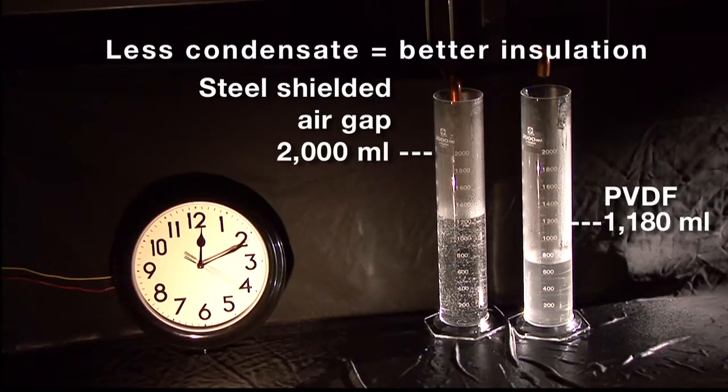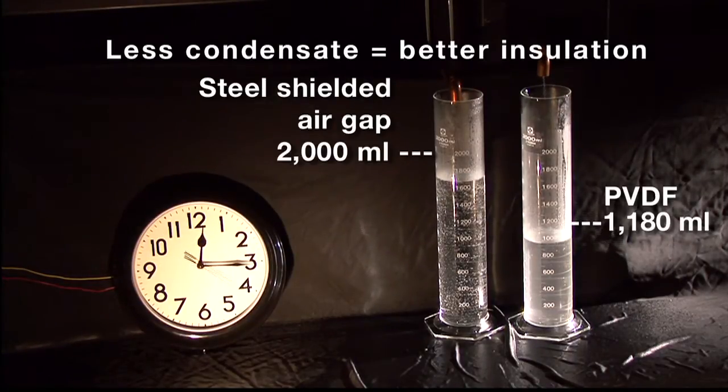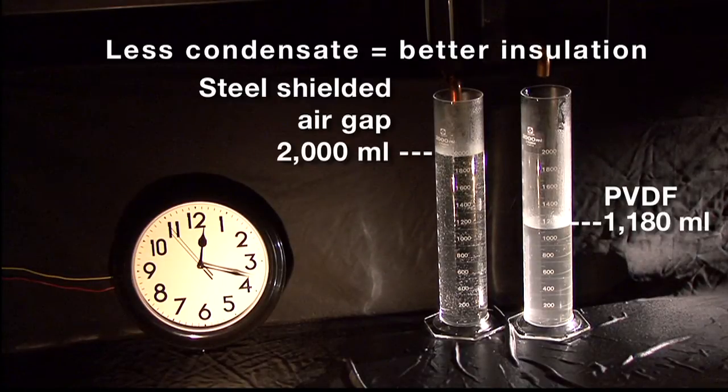In fact, tests performed when we were establishing PVDF's insulating performance guarantee showed that PVDF insulated tubes perform about twice as well as stainless steel shielded air gap insulated tubes.